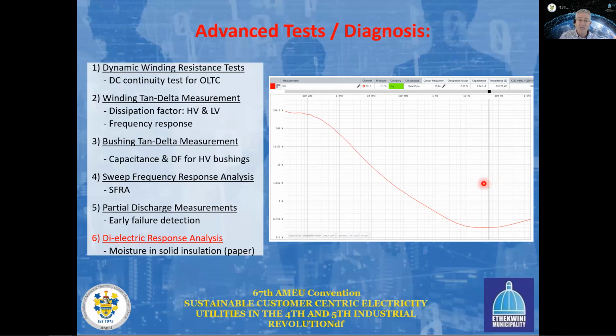This wide frequency measurement then gives us the facility to model the paper in the solid insulation of the transformer. In this case, it measures the paper at 1.1% of the weight of the transformer. Anything up to 2.2% as per IEC 60422 means that this transformer is dry, it's good. From 2.2% up to 3.5%, it's moderately wet. Up to 4.7%, it's wet, and above 4.7%, please don't use that transformer. Don't switch that transformer on in any way.